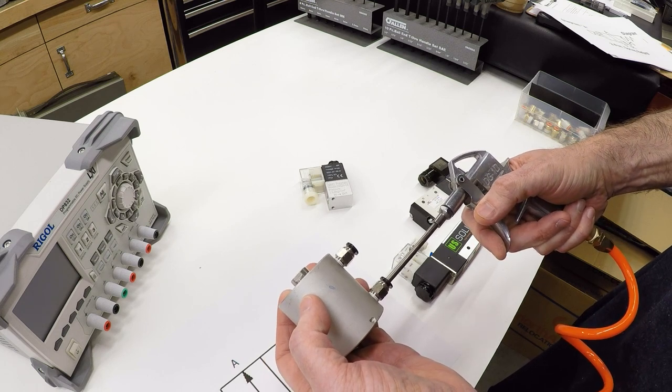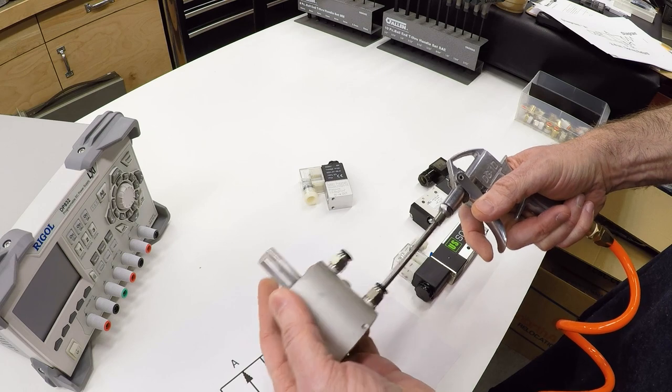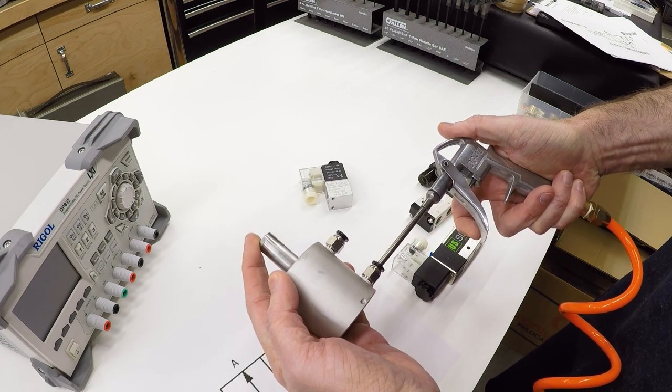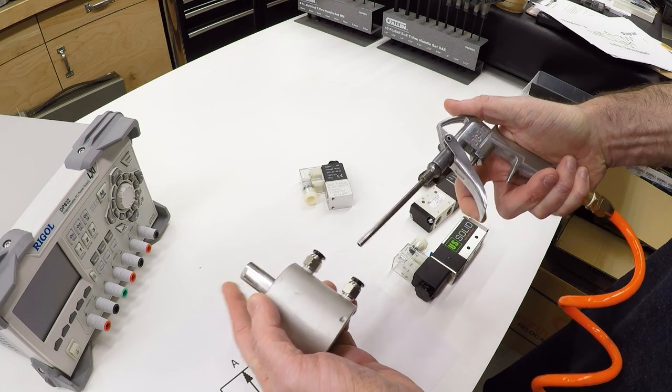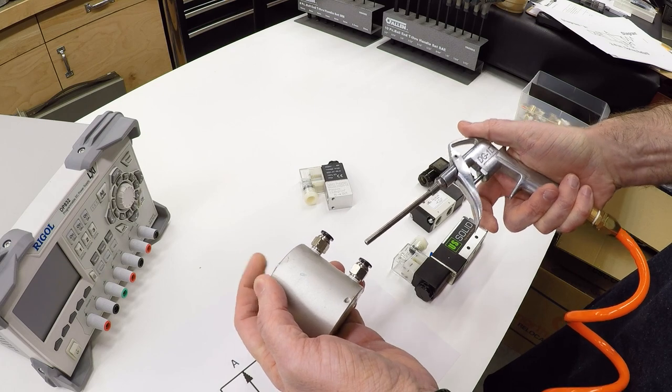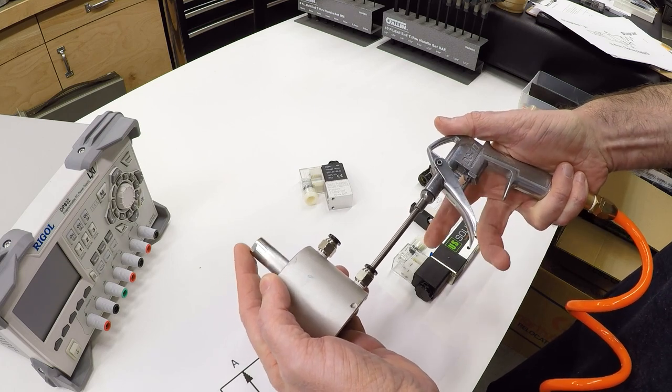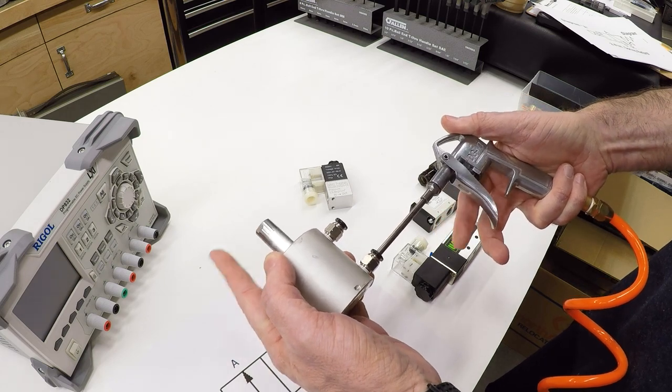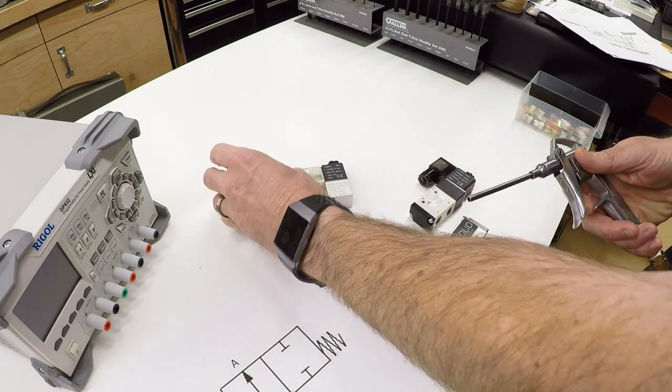However, you can't just turn off the air. In this case, I have extended it, and I've closed the valve, so there's no more air pressure. But I still can't push this back, because in order to push this back, the air has to be able to flow back out of this port. So until I actually vent it to the atmosphere, it can't return. That's what the next kind of valve does.